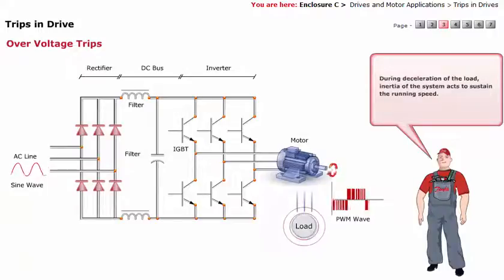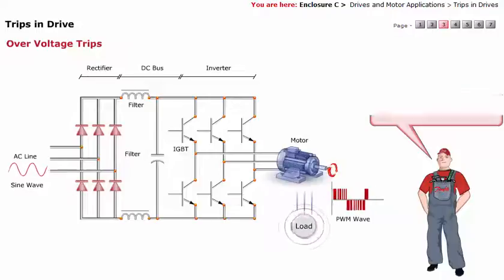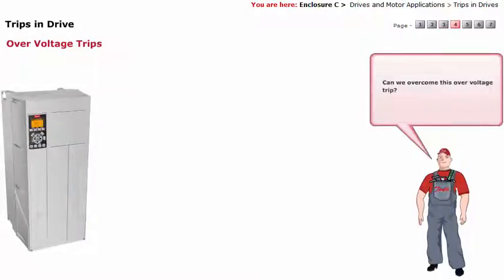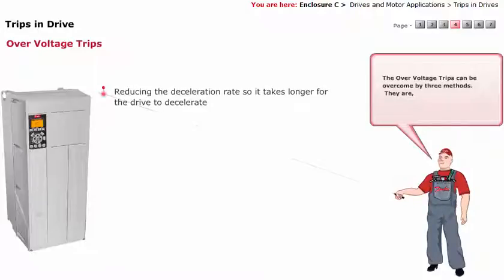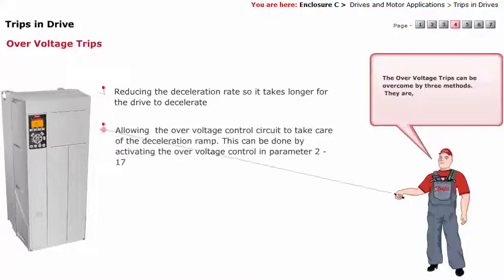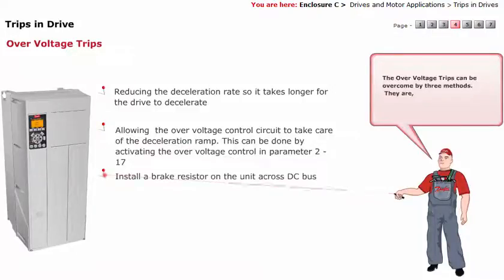Can we overcome this over voltage trip? Yes, we can. The over voltage trips can be overcome by three methods: reducing the deceleration rate so it takes longer for the drive to decelerate; allowing the over voltage control circuit to take care of the deceleration ramp, which can be done by activating the over voltage control in parameter 2-17; or installing a brake resistor on the unit across the DC bus.